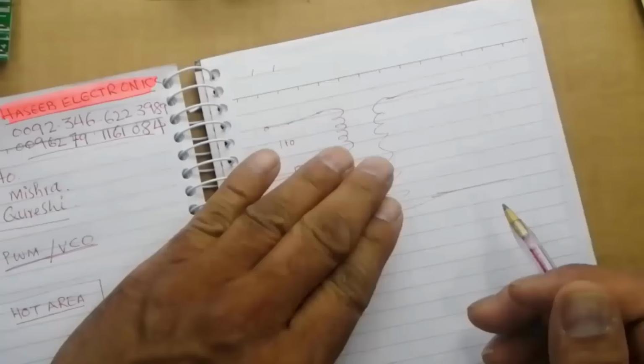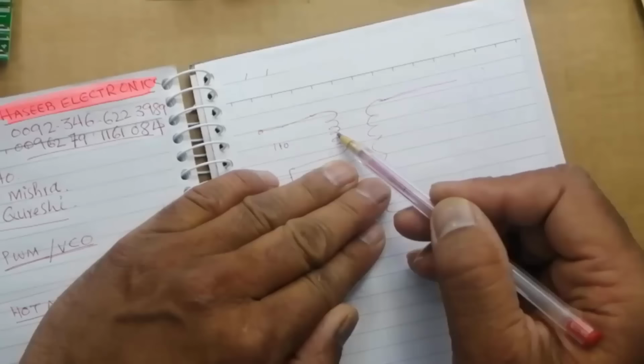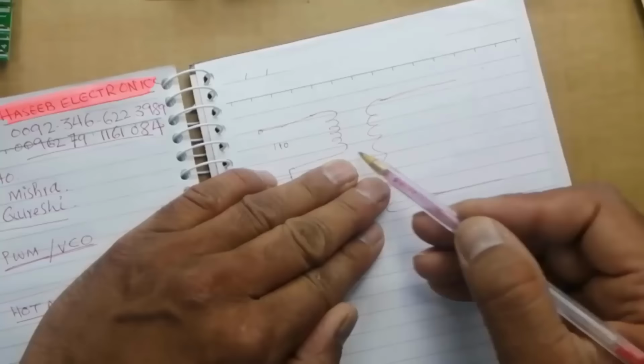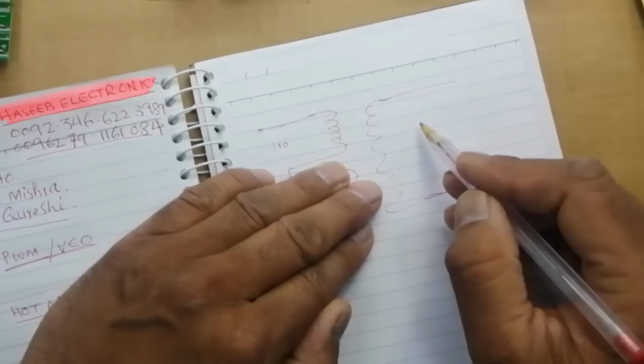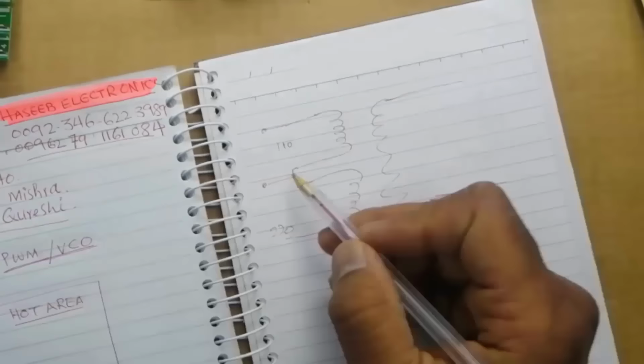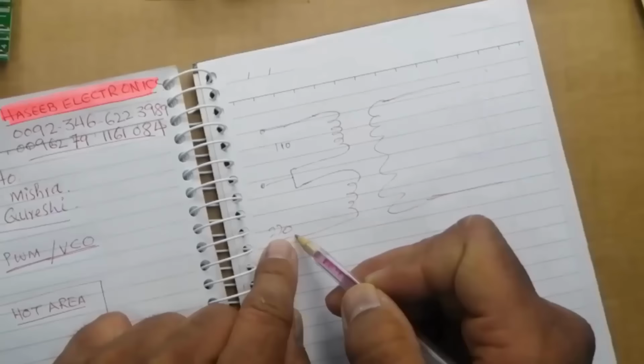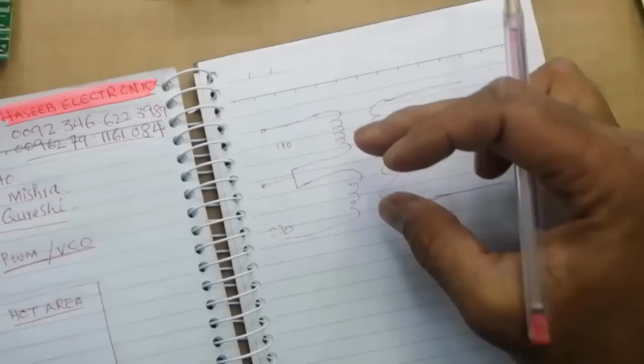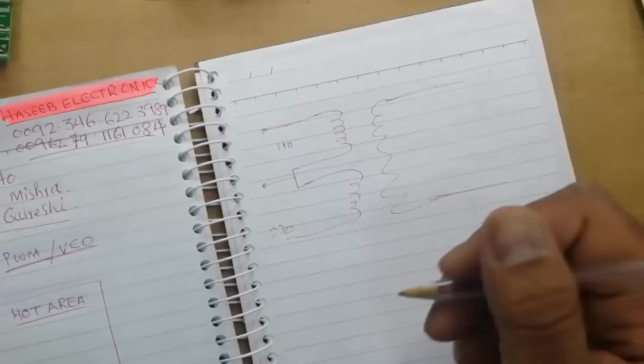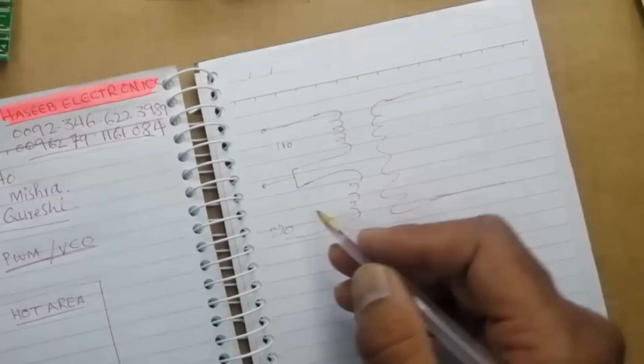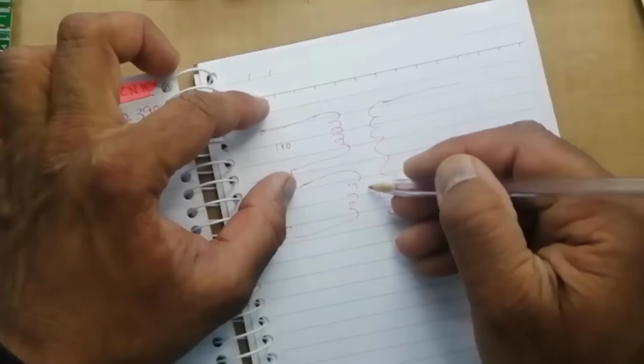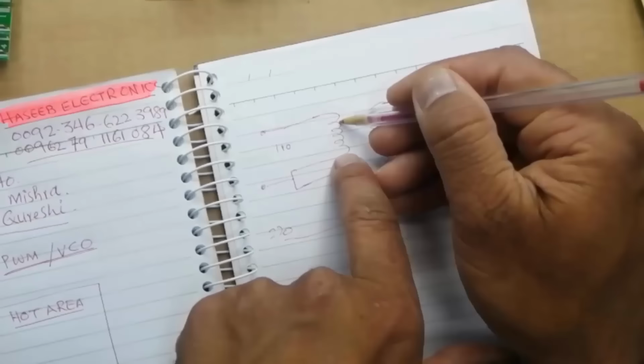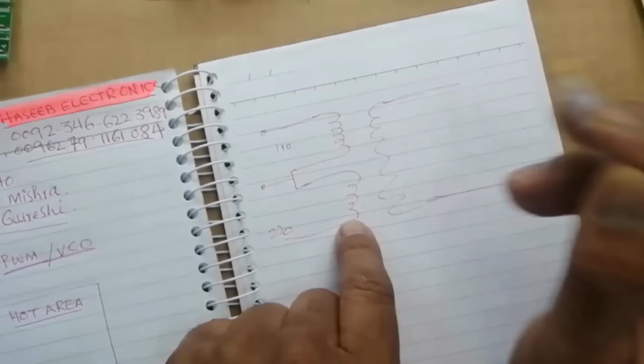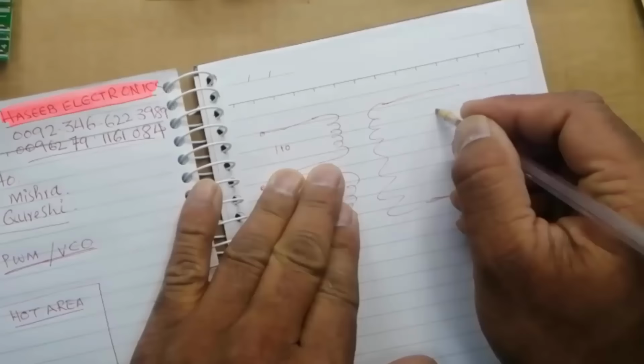When we were applying 110 volt, it was using a small amount of coil. When it is using a small amount of coil, it will give a specific flux to induce voltage in the output. When we apply 220 volt, two coils come in series. When two coils are in series, the inductive reactance XL will increase, so the magnetic field will be the same as it was at 110 volt. Why? Because now the extra 110 volt is dropping here. Suppose if we apply 110 volt, it gives us 9 volt.